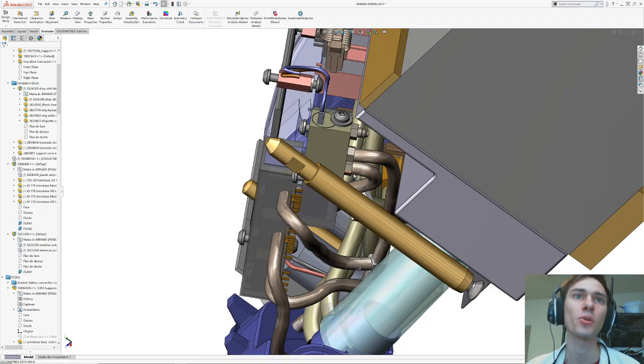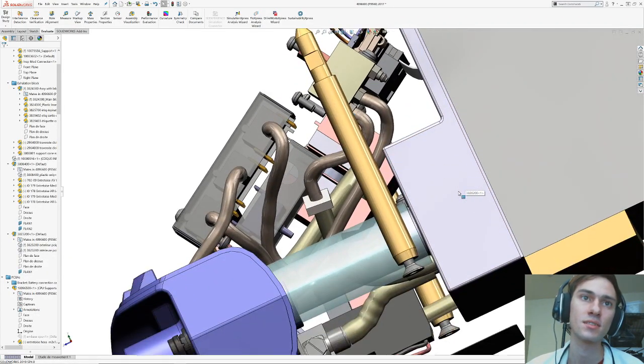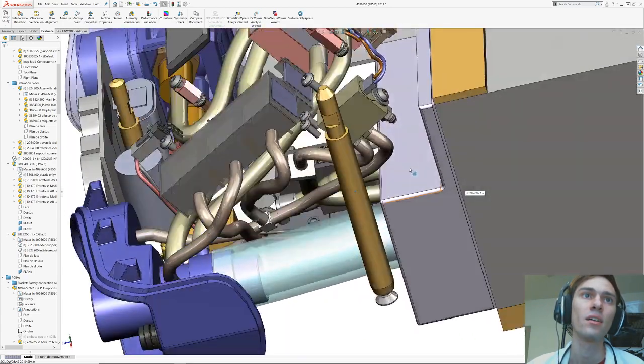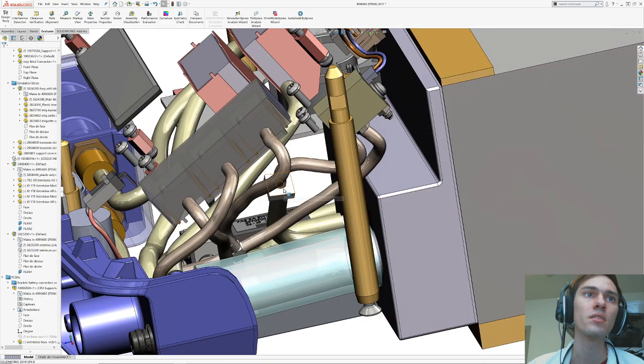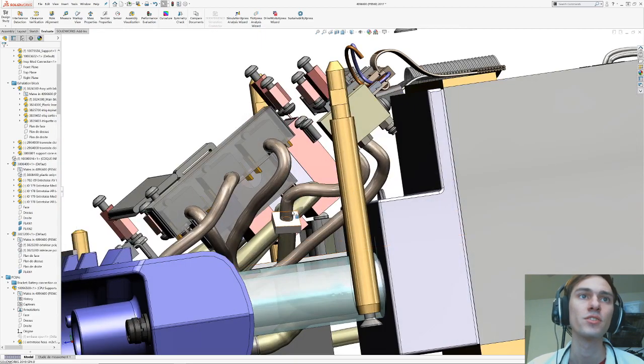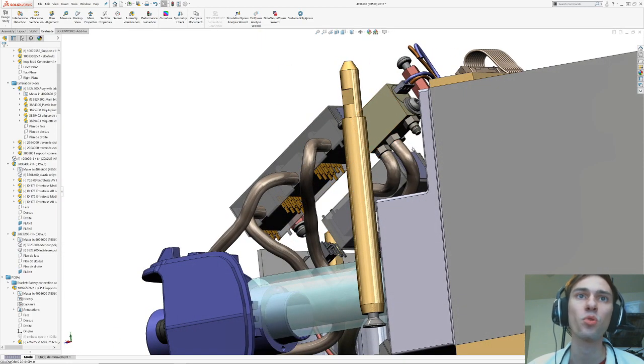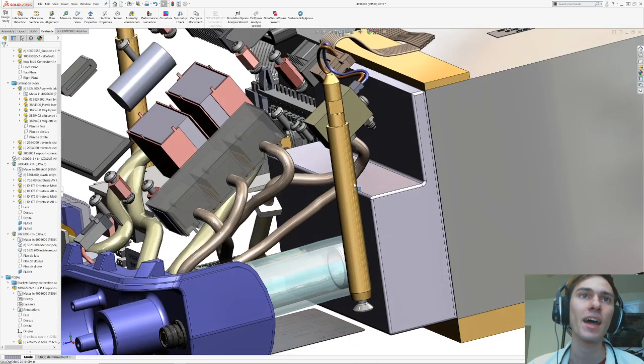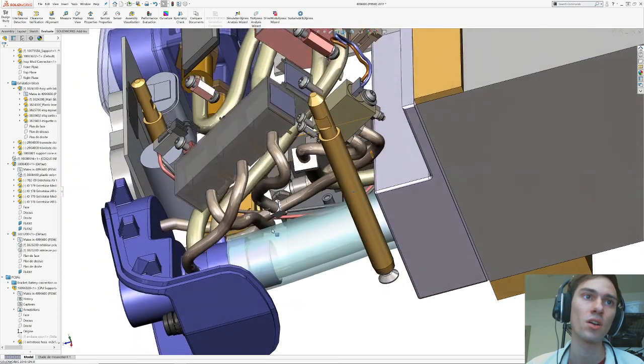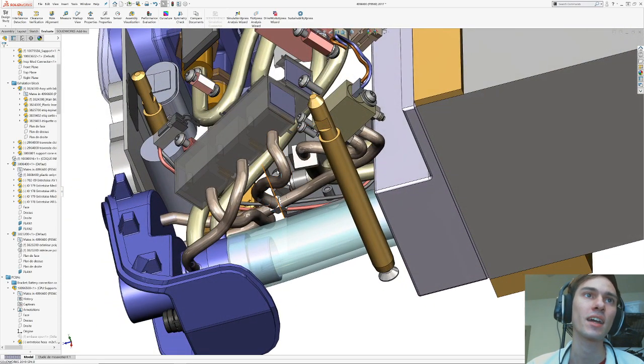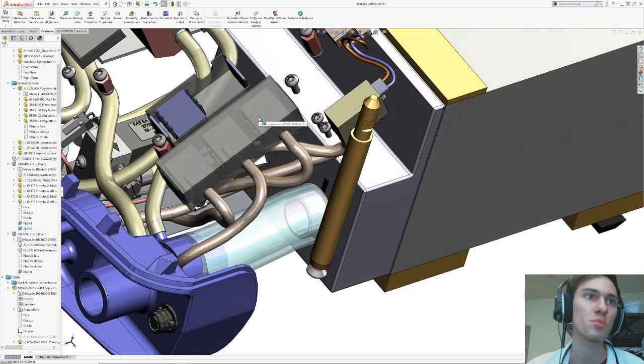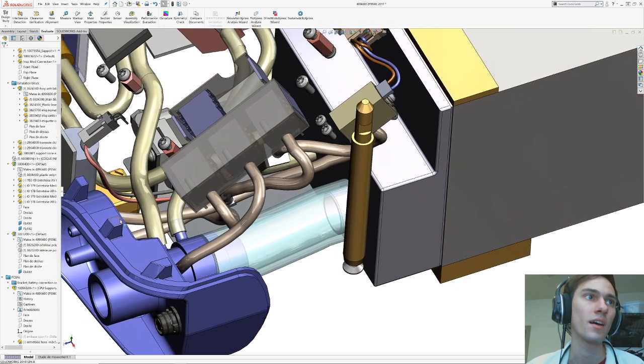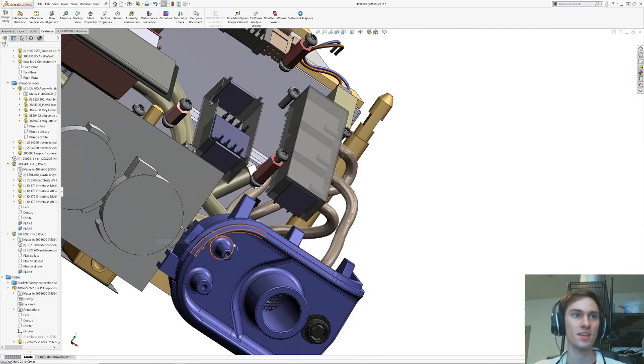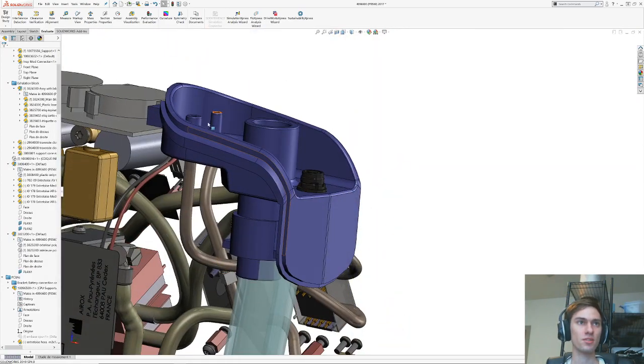So if we go back to SolidWorks, turbine flow is this one right here. So this is port 1. That's port 2, and that connects to the exhalation pressure sensor, which we know because that connects to this one right here. So this is going to be the exhalation pressure sensor. So this tube right here is the exhalation pressure sensor port. That one right there.